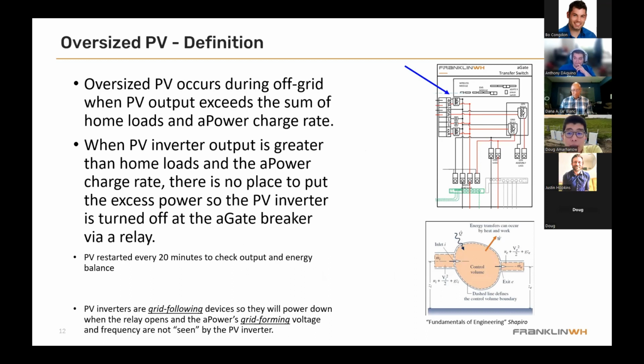Do you guys understand that concept? Because what we do is islanding. That means the customer is able to use the solar to increase the output of the system, so you have both the output of the PV and the battery at the same time. This is a big advantage we have over Tesla, because they have very restrictive rules on this. A lot of times Enphase doesn't work very well with Tesla for islanding. It kind of just shuts off the PV in the middle of the day because there's so much solar, the batteries are probably full, and there's nowhere for that power to go.